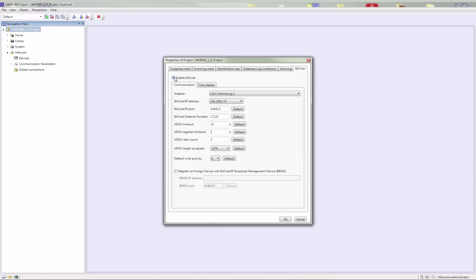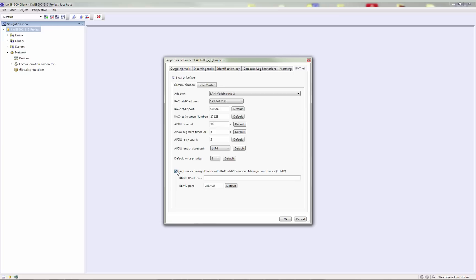The LWEB900 server can register with an existing BBMD in the BACnet IP network as a foreign device. This functionality is used if the LWEB900 server is located as a single BACnet IP device on a remote IP subnet.